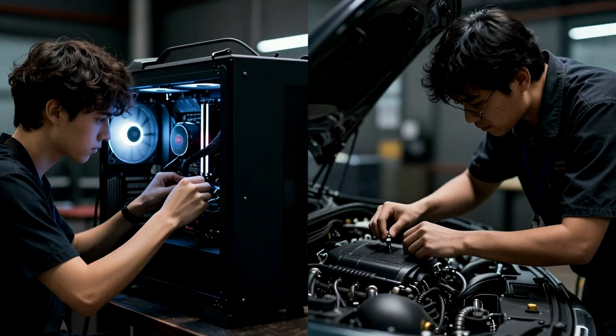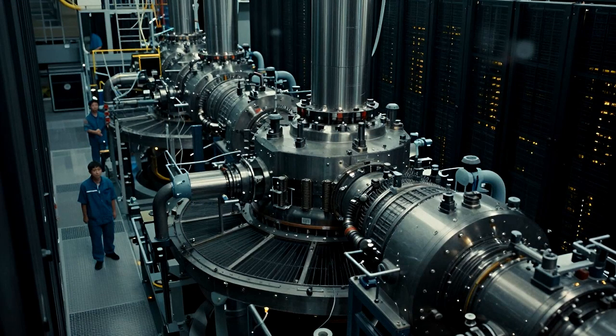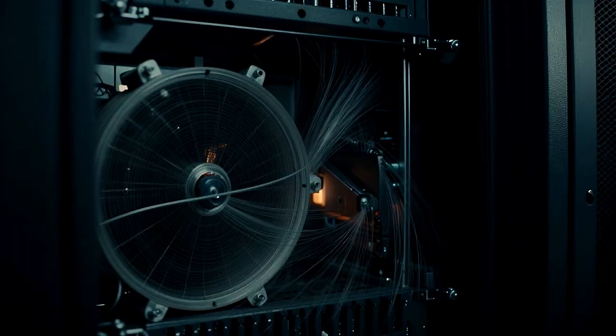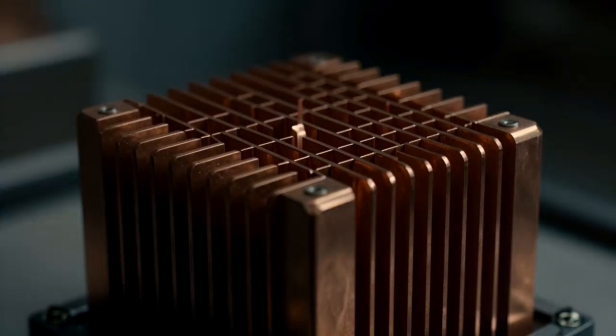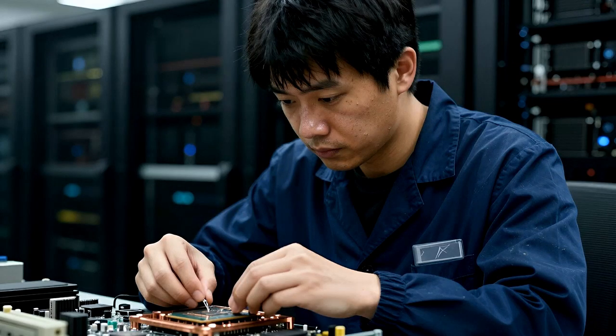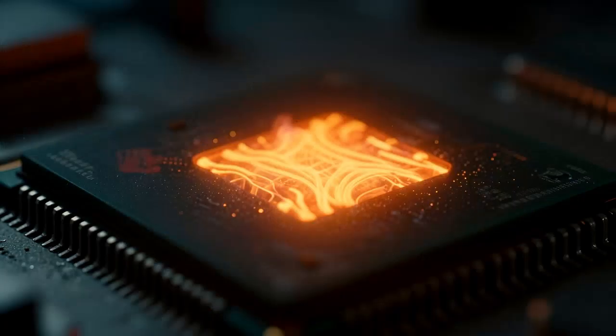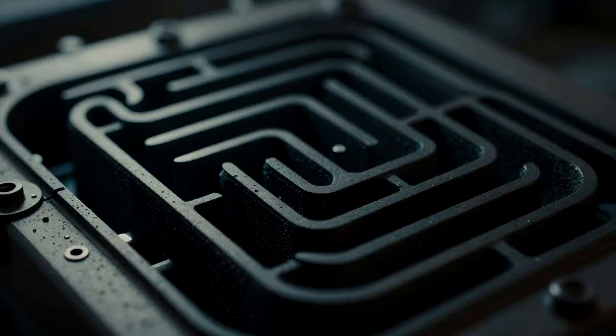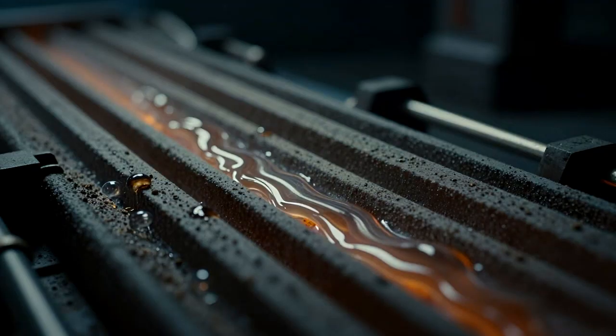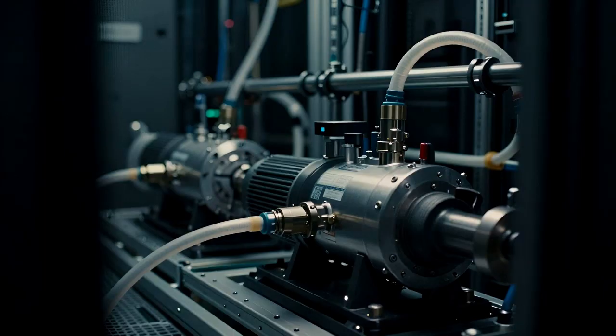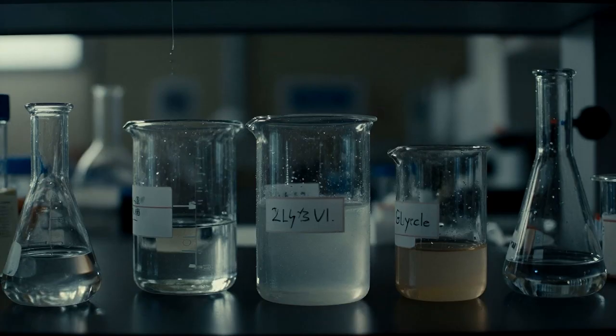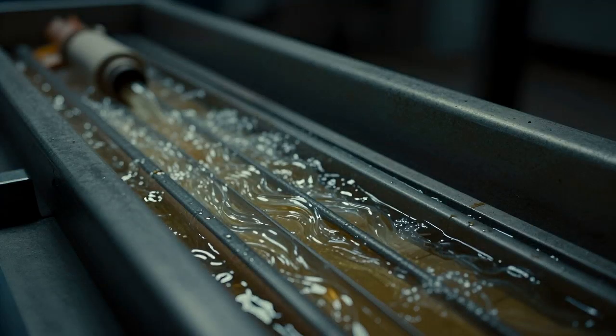It operates on a principle highly familiar to any automotive mechanic or personal computer gaming enthusiast, but scaled up to an exacting, industrial extreme. Instead of relying on inefficient air to ferry heat away, these systems attach highly conductive metal heat sinks, typically fashioned from copper or aluminum, directly onto the surface of the hottest heat-generating components. These custom-machined cold plates are intricately carved with microscopic internal channels known as microfluidics. A specialized closed-loop system pumps a chilled liquid, often a formulated water and glycol mixture, or a synthetic dielectric fluid, through these tiny channels within the cold plate.